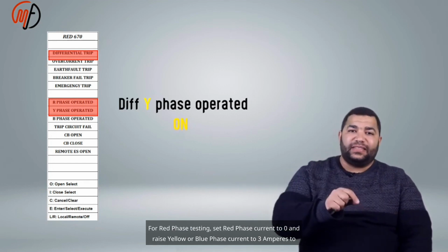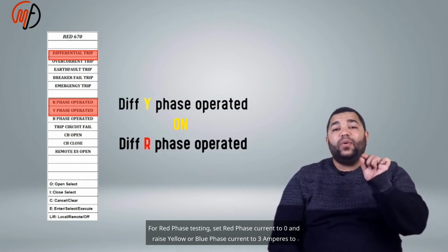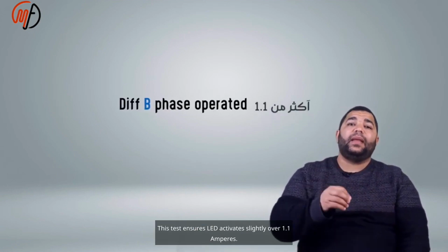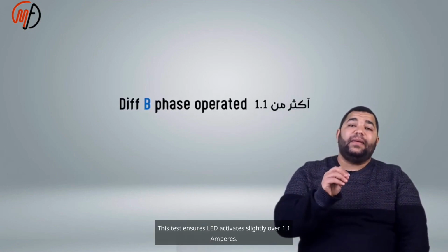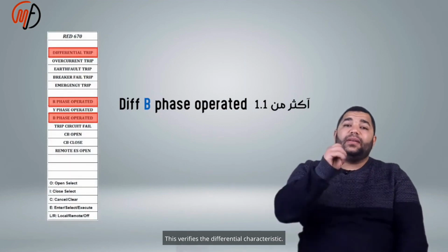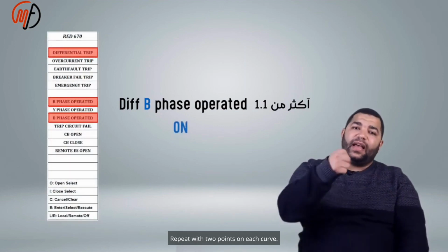For red phase testing, set the red phase current to 0 and raise the yellow or blue phase current to 3 amperes to stabilize I bias. Then, raise the red phase current over 1.1 amperes. The red phase LED lights up. This test ensures the LED activates slightly over 1.1 amperes. This verifies the differential characteristic.